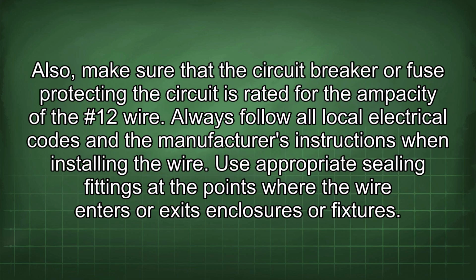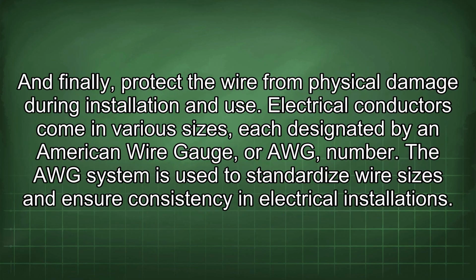Also, make sure that the circuit breaker or fuse protecting the circuit is rated for the ampacity of the #12 wire. Always follow all local electrical codes and the manufacturer's instructions when installing the wire. Use appropriate sealing fittings at the points where the wire enters or exits enclosures or fixtures. And finally, protect the wire from physical damage during installation and use.